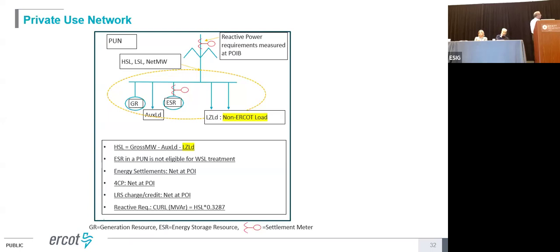Now, if you have generation behind the meter and you want to monetize that - last year around the same time, my boss asked me, 'We're getting a data center, 400 megawatt data center, and they have maybe 500 megawatts of backup gen.' The current private use network construct may not provide enough incentive for them to register as a market resource. So they might come in as what we call settlement only, where they can come on and come off anytime they want to. ERCOT has no visibility into that. And that's what I've been working on.